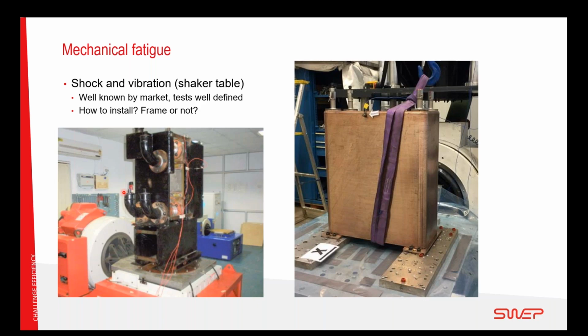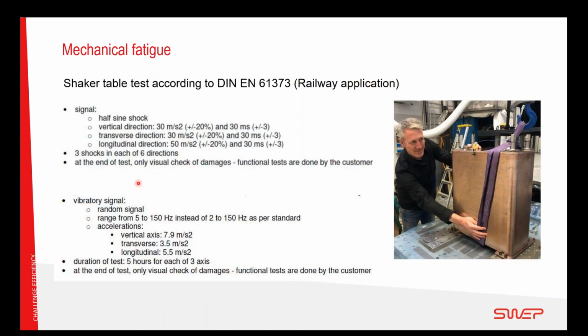To the right is a test we did on our heat exchanger. Some more details about this. The standard is taken from a railway application, EN61373. It's shock and vibrations. And here is the test described, the shock loads in each of the 3 directions. You go plus minus in both directions, so that's 6 shocks done on the heat exchanger. Since we don't know exactly in what direction the heat exchanger is mounted, it's been tested here for the highest value for all directions on our heat exchanger.